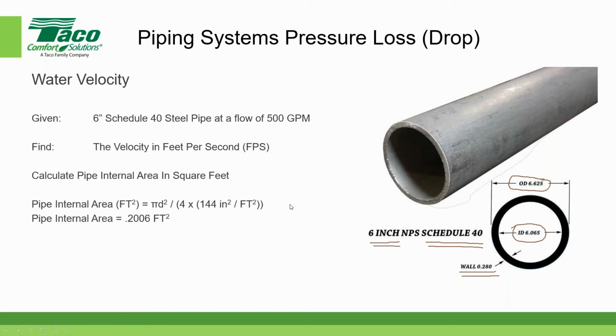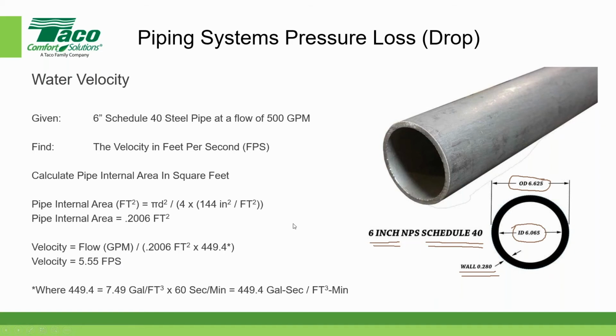Now, the next thing we want to figure out is, what is the actual velocity? Well, the velocity is equal to the flow divided by the area in square feet, and we have this constant here, 449.4, and I'll show you in a second where that comes from. If we plug in the numbers, we come up with a velocity of 5.55 feet per second. We're plugging in 500 gallons per minute divided by this value over here. And the 449.4 is the conversion from gallons per minute into cubic feet per second, because if we have cubic feet per second divided by square feet, then we get feet per second.